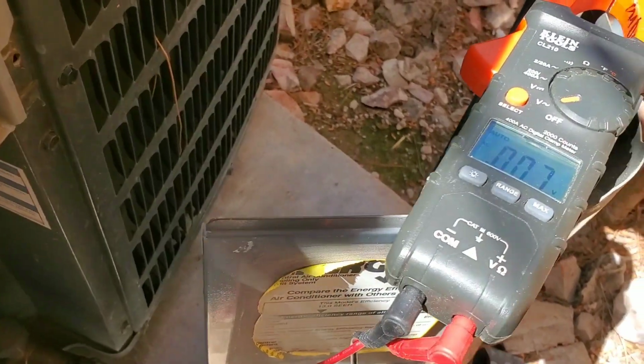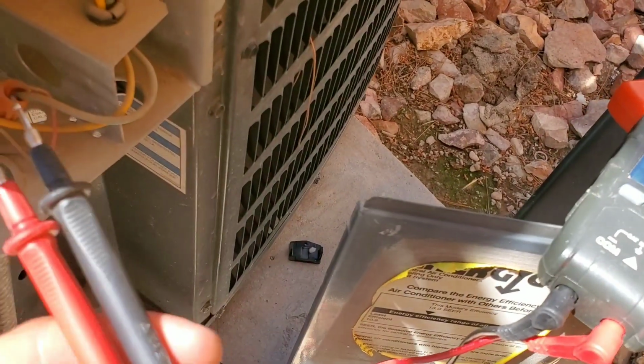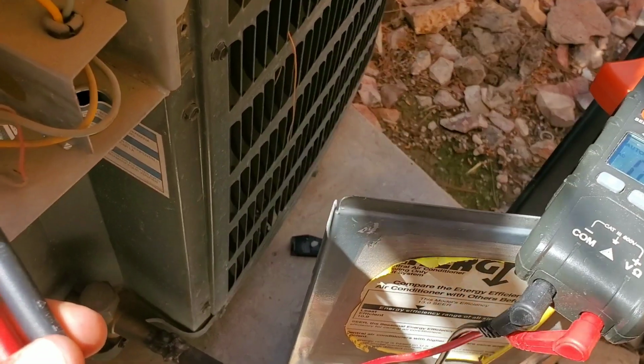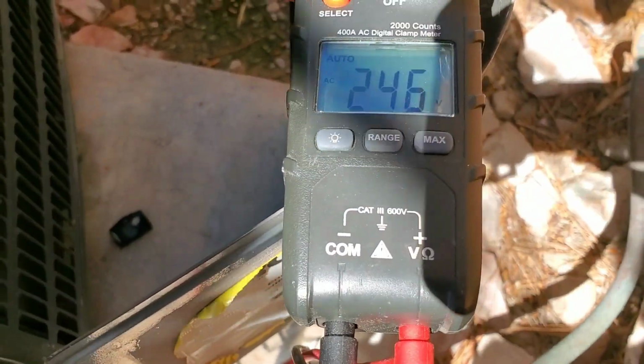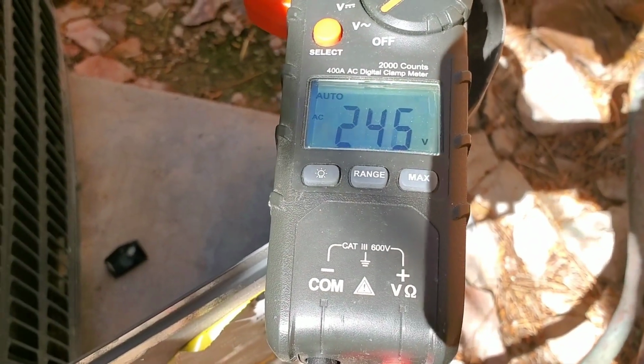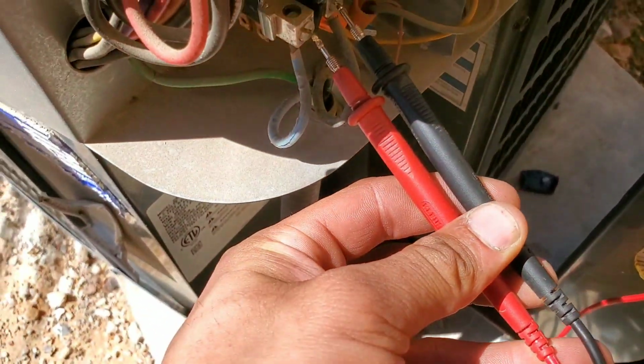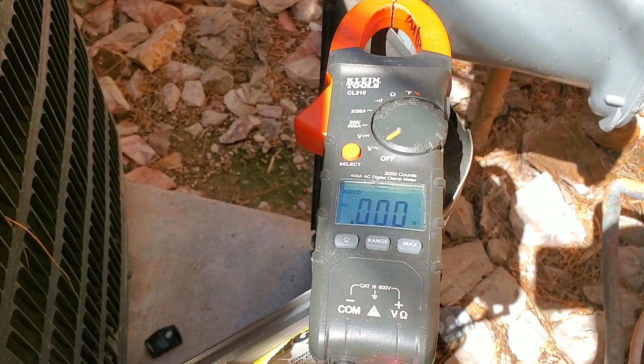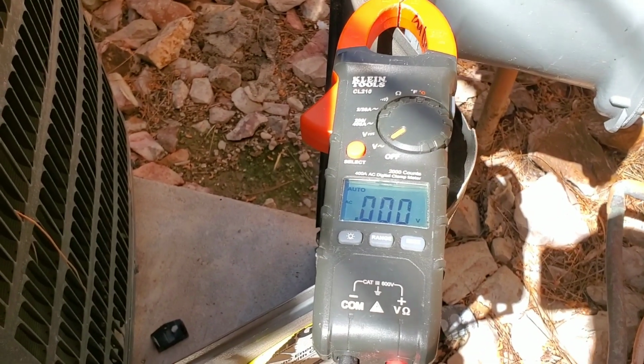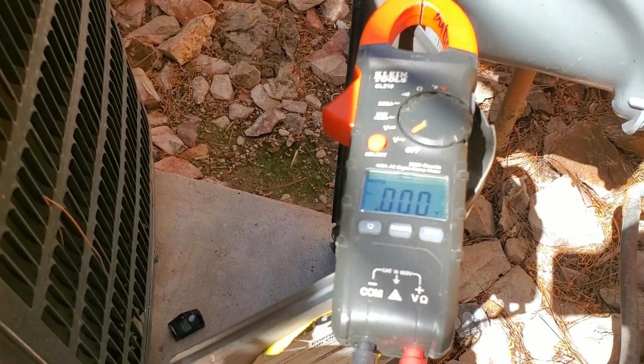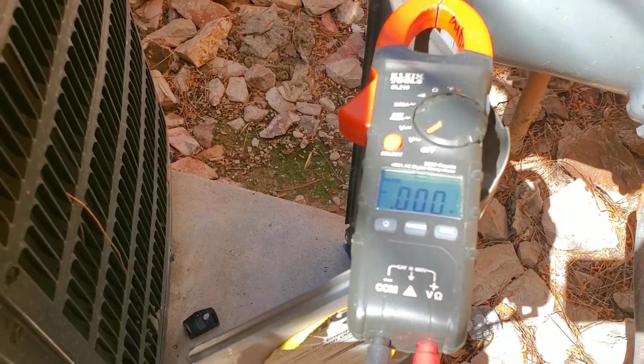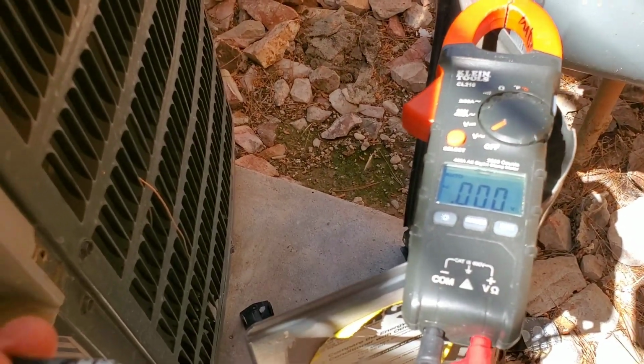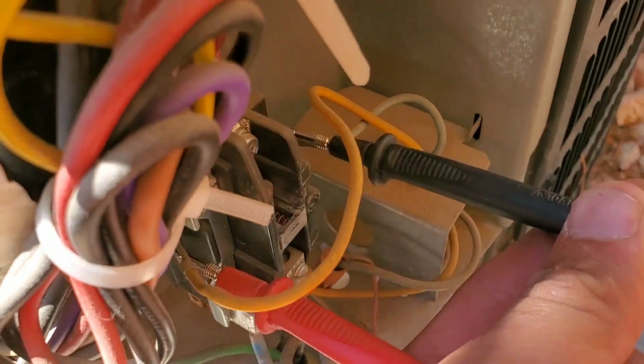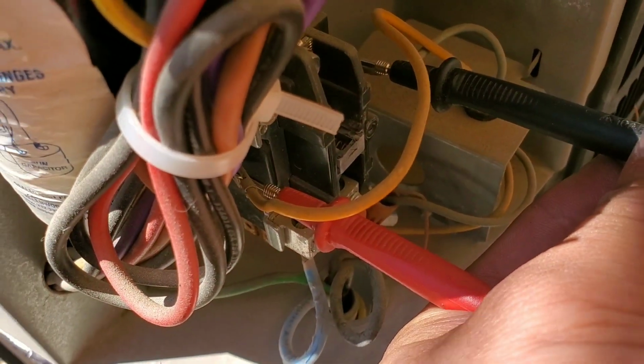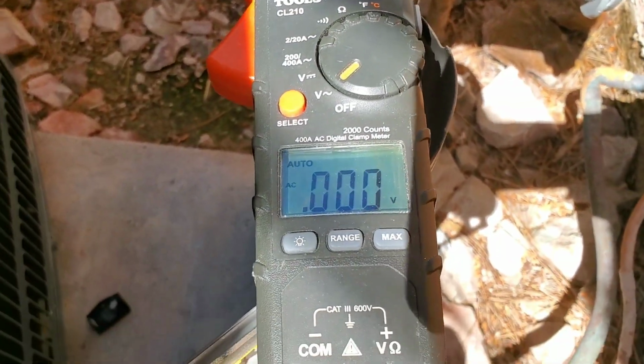Now what I'm going to do is I'm going to take my voltage. This is my incoming voltage. I should have 240 volts, which I do. Now I'm going to check my low voltage. My thermostat is set to cool. I did drop the ambient temperature for the set cool point. And here, I should have 24 volts at my low voltage wires, and I do not have voltage.